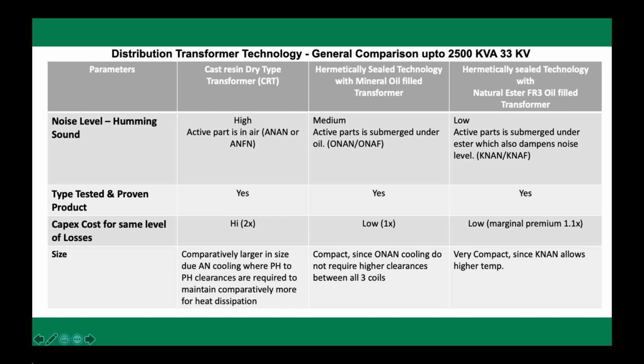When it comes to the application, a lot of people ask, okay, but has your transformer been type tested? Transformer type testing has nothing to do with the liquid system. Transformer type test, when it comes to the short circuit, whether it's a mineral oil filled, a natural ester filled or a synthetic ester filled, all transformers will be the same. When it comes to the impulse, yes, you have to give consideration. And when it comes to the temperature rise, all the transformer manufacturers and OEMs today offer you a technology which is well type tested and safer.